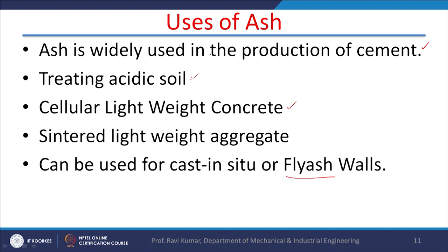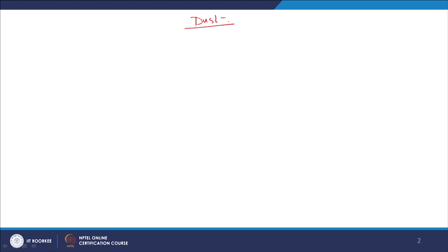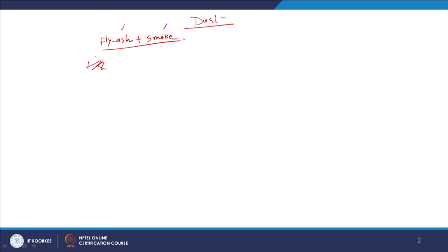In a power plant there is a lot of dust. Dust is not necessarily only fly ash; it also includes smoke. Smoke and fly ash can be differentiated through particle sizes. Smoke particles are normally less than 1 micron, and because of their very tiny size they remain suspended in the air for a long period. Fly ash particle size ranges between 10 to 100 microns.